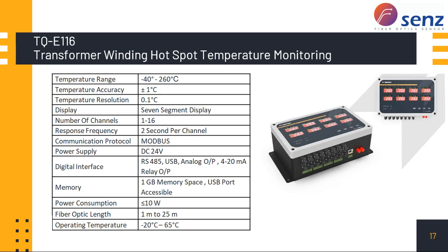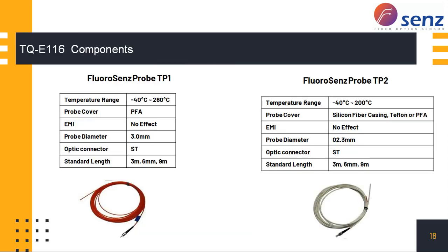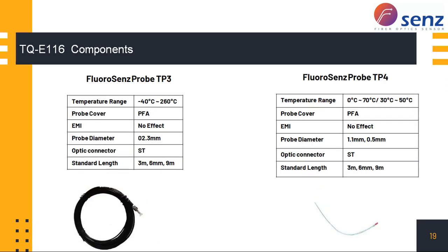There are different fiber optics available, which can be used as a sensor for transformers or for any other purposes. So these are the possible types of sensors which are available. This one, the TP1, is up to 260 degrees. TP2 is up to 200 degrees centigrade. So there are different applications. The diameters and the lengths are available, so that you can choose for your application. We can help you. Some small diameter probes are also available for smaller applications, the TP4, which is 1.1 mm or even 0.5 mm.